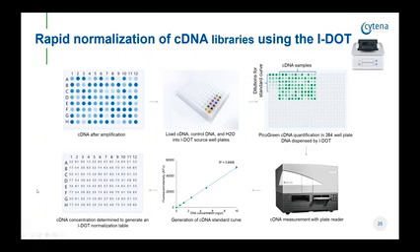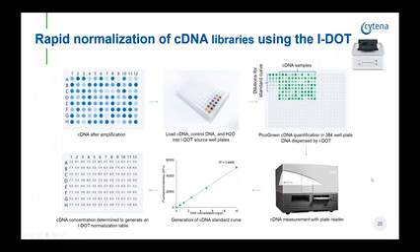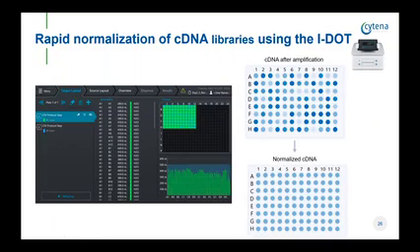The other example is normalization. To normalize DNA samples such as cDNA libraries, different volumes of buffer and DNA have to be dispensed for each sample. We did this by loading 96 samples onto an IDOT source plate and dispensing those for subsequent quantification using an intercalating dye on a plate imager — in this case a PicoGreen assay at reduced volumes. The results from the plate reader can be automatically translated to a CSV file or Excel table that can be loaded into IDOT Assay Studio within minutes, and the IDOT can then be set up to dispense and normalize 96 cDNA libraries in parallel.